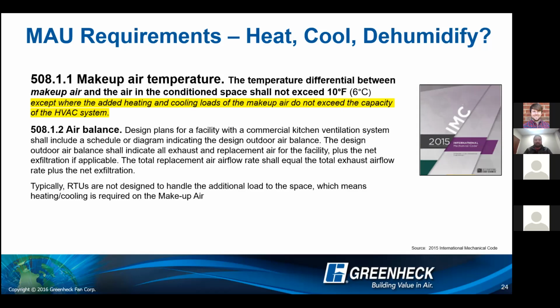But it's the second portion. Except where the added heating and cooling loads of the makeup air do not exceed the capacity of the HVAC system. So that's giving a lot of deference to the designing engineer to say, yep, my system can handle this. I'm going to bring this air in such a fashion that I'm only going to heat it, I'm going to heat and cool it, or I'm going to dehumidify it. It just gives a lot of flexibility to the designing engineer. There's a lot of deference to you all.